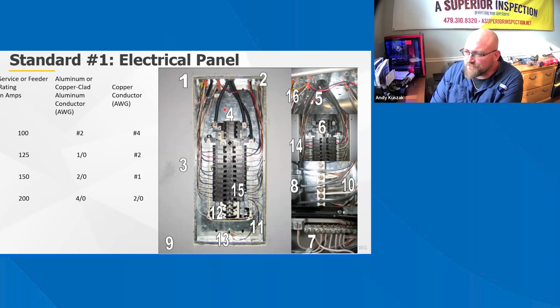So number 4, refer to the following table when inspecting the service or feeder cable. Over here on the left-hand side, you're looking at 100 amp service rating. So you should have a minimum of number 2 aluminum and number 4 copper. And then as we go down the list here, 125 goes to 1-aught or number 2, 150 amp goes to 2-aught or number 1, and 200 amp service goes to 4-aught or 2-aught for copper.